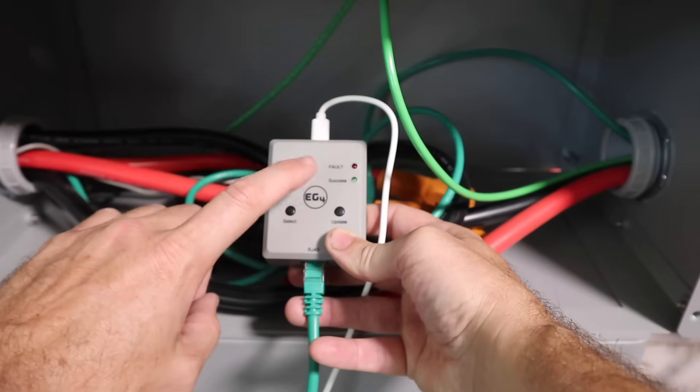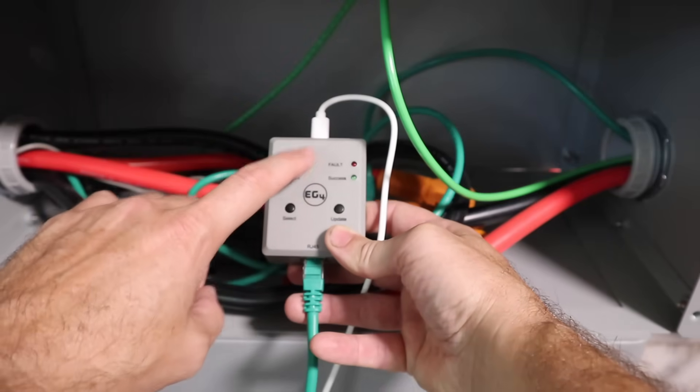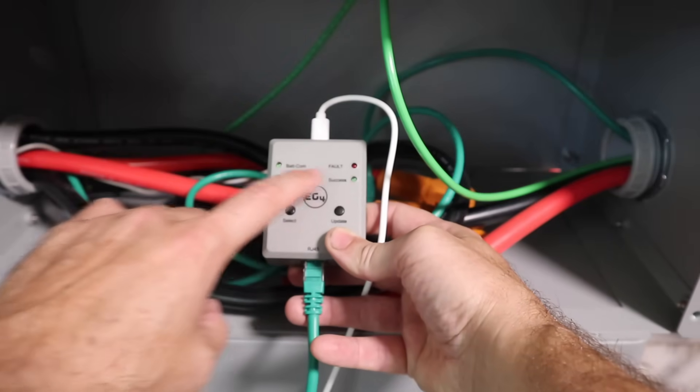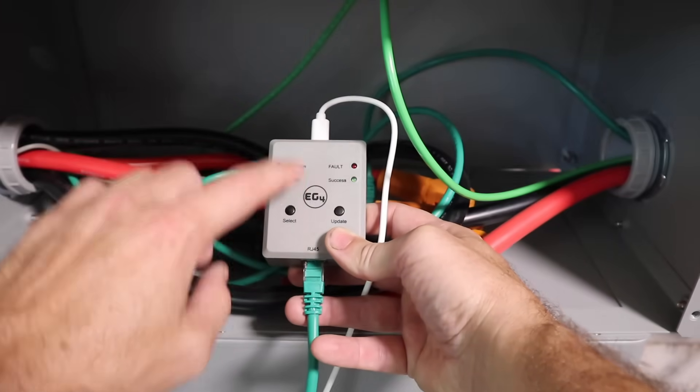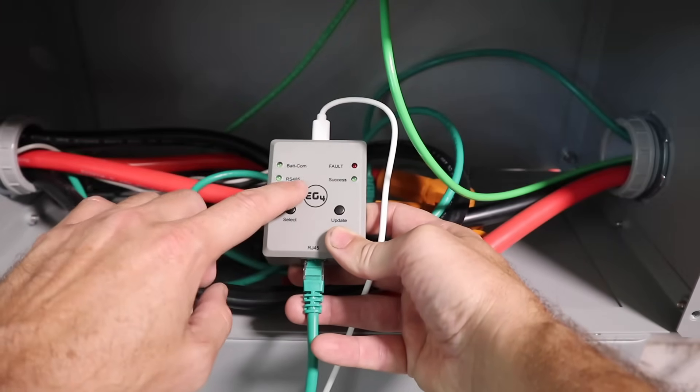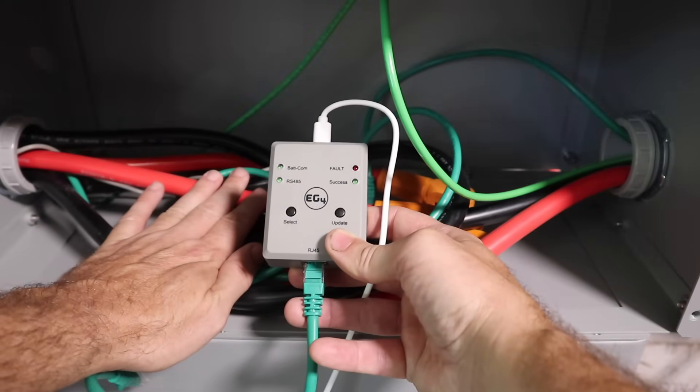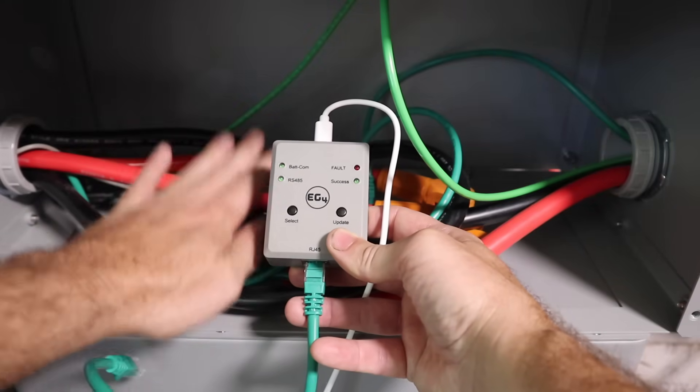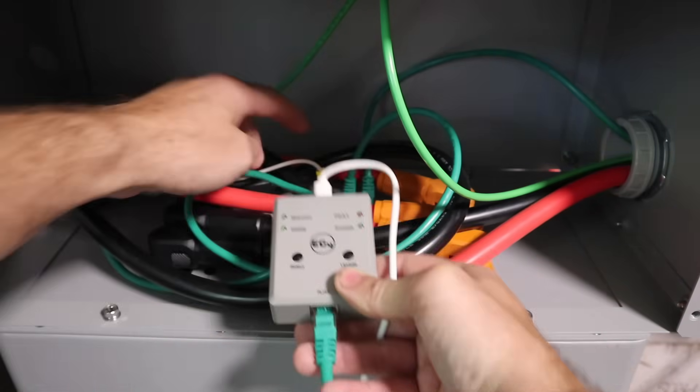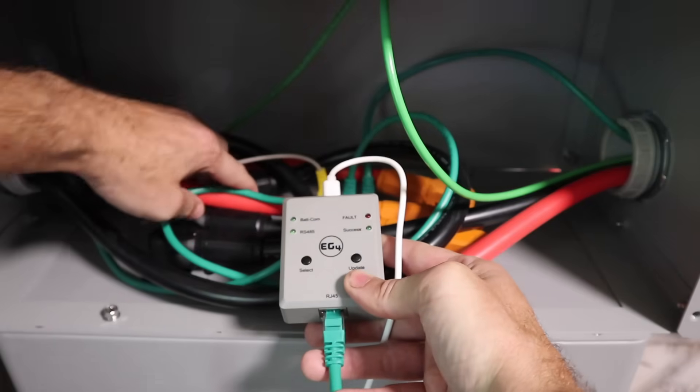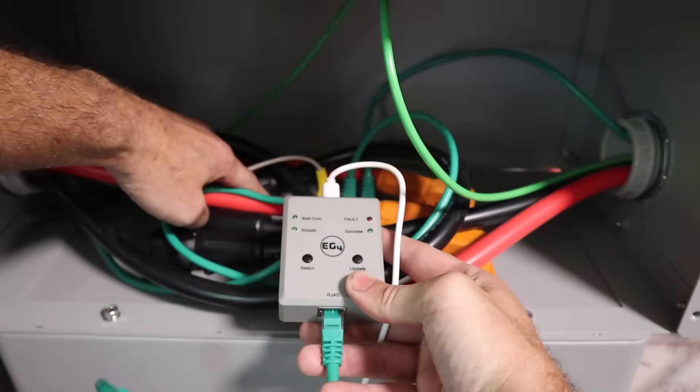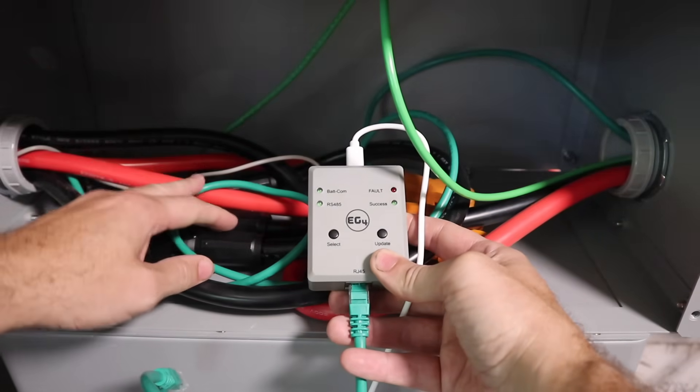Remember, you need to take off or delete the LLS firmware that you put on here, replace it with the 280 amp hour wall mount battery firmware, and then you can update this. And if you want, you can play with those ID switches back there. It didn't seem to make a difference for us on the LLS batteries.